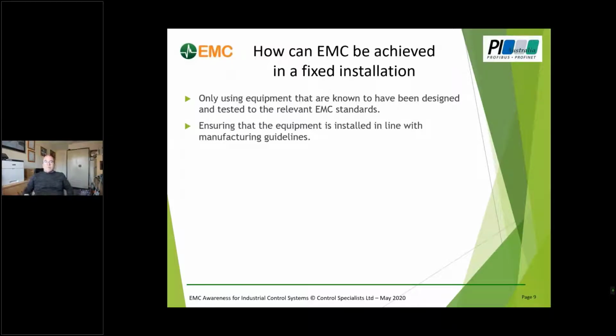We ensure the equipment is installed in line with manufacturers' guidelines, which might seem obvious, but I've lost count of the times I've gone on site on a PROFIBUS network where there've been problems. My analyzer tells me everything is fine, yet clearly it isn't. I just cast my eye over it from an EMC point of view and got them to check whether their installer had installed this drive or bit of kit in line with the manufacturer's guidelines. Invariably they hadn't, and when they did, the problem went away. So you don't always need complex equipment.